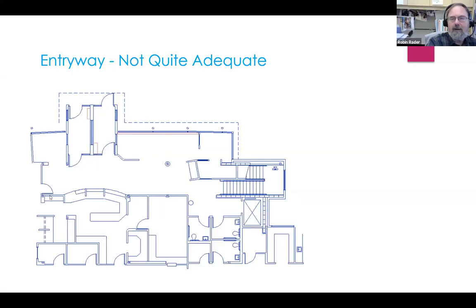Now you'll notice that we did do something correct as far as the receptionists. They have a fully closed area, and so their counter is, say, 4 foot high, and that protects them from cold air. And so our receptionists are fully protected from the cold air, but the people waiting in the occupant area are not, and this was a problem.